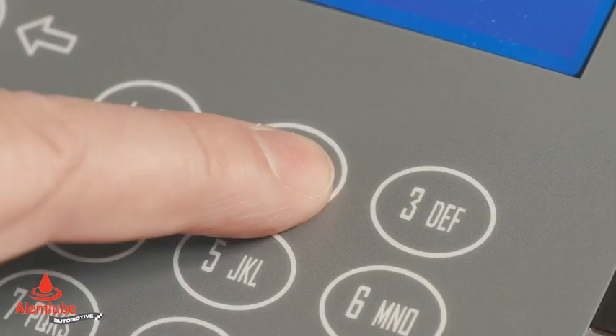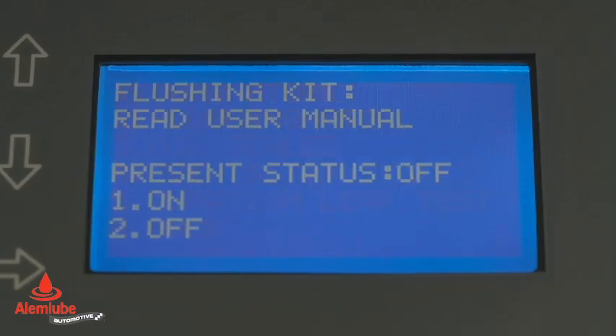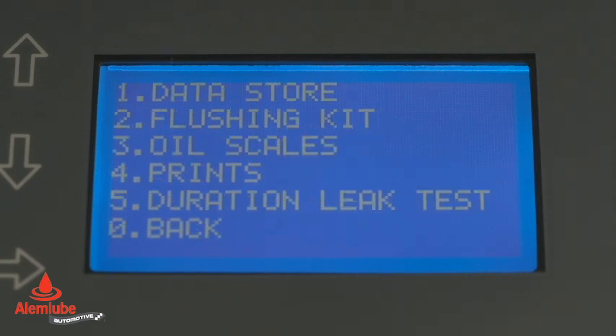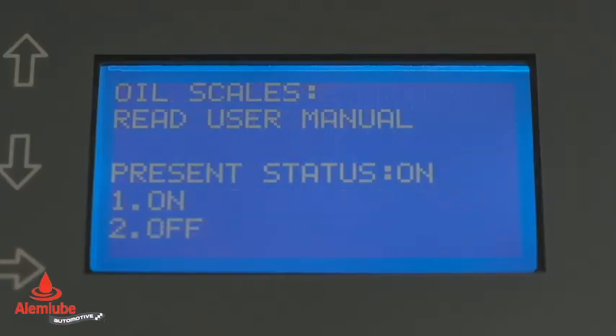By typing 2 it is possible to set the washing function, which by default is deactivated and can be activated when the optional kit is purchased. By typing 3 it is possible to disable the oil scales. This feature allows you to use the equipment even without the oil scales, checking the quantities of oil directly on the graduated bottle.